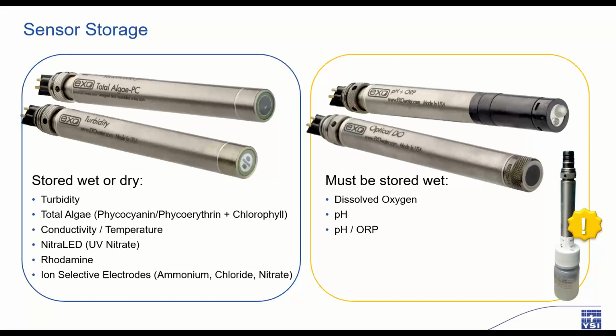You need to examine the face of these probes to make sure that they do not have a film or any other debris on the face that might interfere with readings or calibrations. If they do, simply use a lint-free cloth to wipe them down. And if there is severe buildup, you can even use a piece of moistened 3M Scotch-Brite to gently buff them clean. Do not use this pad for cleaning DO, pH, or other ISE sensors. It's a little too rough for them.